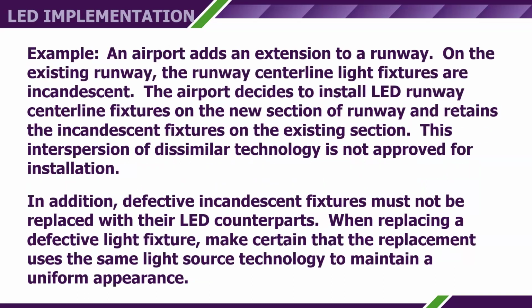It goes on to give us an example in the advisory circular. It says an airport adds an extension to a runway. On the existing runway, the runway centerline light fixtures are incandescent. The airport decides to install LED runway centerline fixtures on the new section of runway and retains the incandescent fixtures on the existing section. The FAA says this interspersion of dissimilar technology is not approved for installation. It goes on to tell us that, in addition, defective incandescent fixtures must not be replaced with their LED counterparts. When replacing a defective light fixture, make certain that the replacement uses the same light source technology to maintain a uniform appearance.